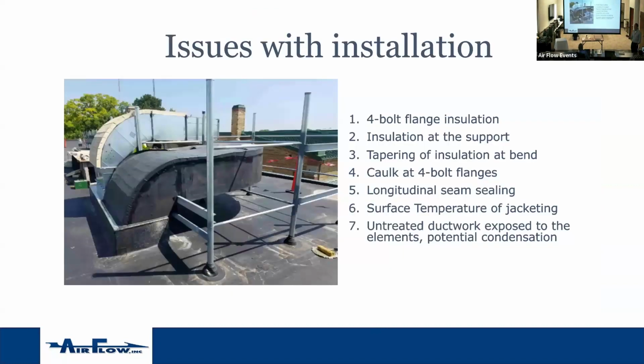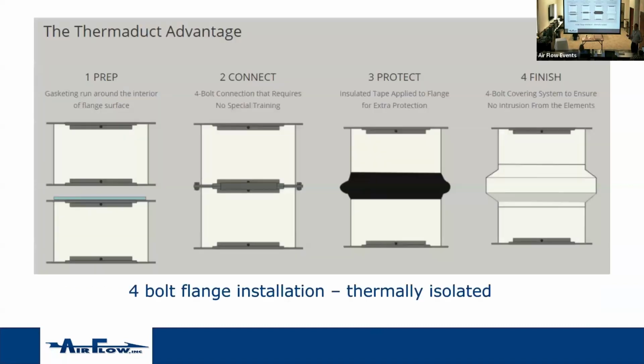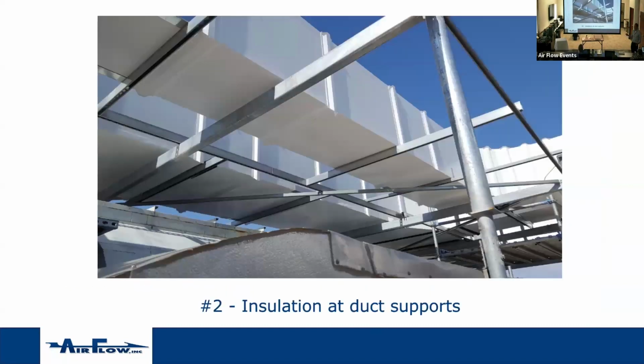Anyway, so we're going back. I really want to show you just one slide. We talked about this. This is great, right? Now I want a couple of things to think about. You bring that metal ductwork out there, you set it on the structure. Is the insulator ready to go the moment that they get out there? No, that ductwork is gonna be sitting there for a little while. So odds are, even if they've taped, they put the blue sticky tape on the outside, there's gonna be some condensation in that duct right when they start it up, assuming that it's not ideal weather conditions, right?